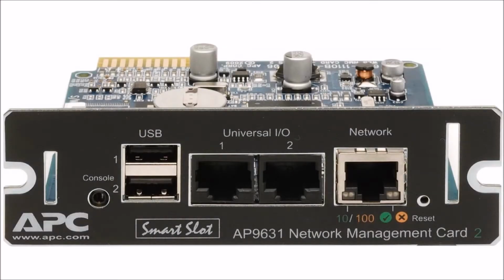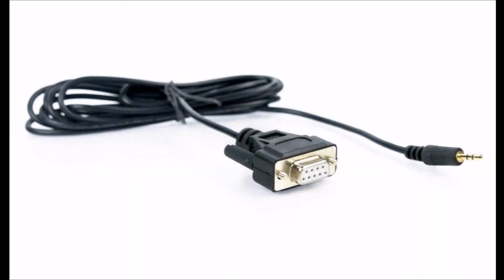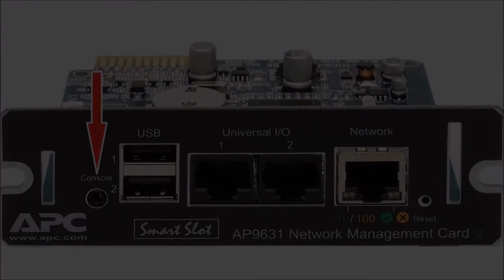In this video, we'll be using the Network Management Card 2 boot monitor to recover and upgrade firmware. For this, you will need a Generation 2 network card, such as in the AP9631 card pictured here, and its cable, the 940-0299 cable, which plugs into the console port pictured here.